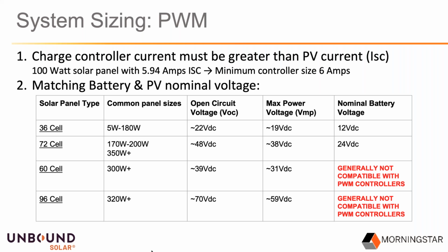There are common panel sizes in that second column. The voltages, open circuit and max power voltage, are approximate; that's going to vary depending on the wattage. And then there's the nominal battery voltage that the panel corresponds to. So I'll quickly run through this first row with 36 cell panels. These are typically about 5 watts up to 180 watts, with an open circuit voltage of around 22 volts and a max power voltage of about 19.